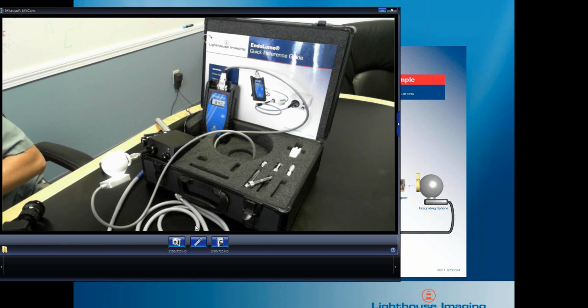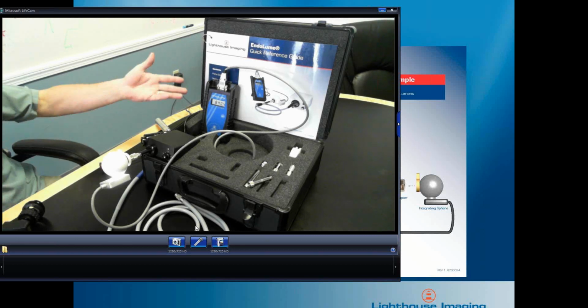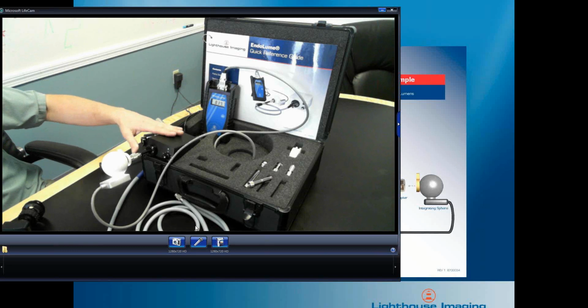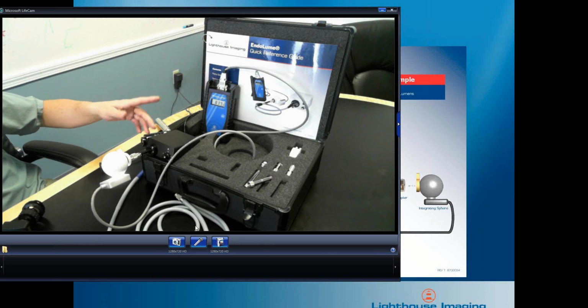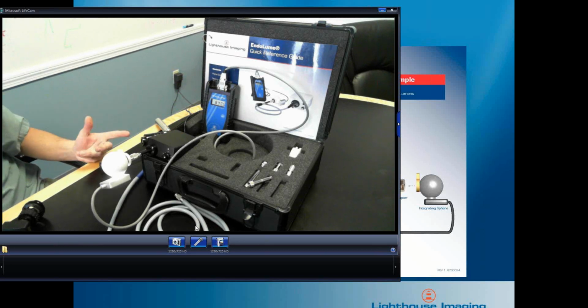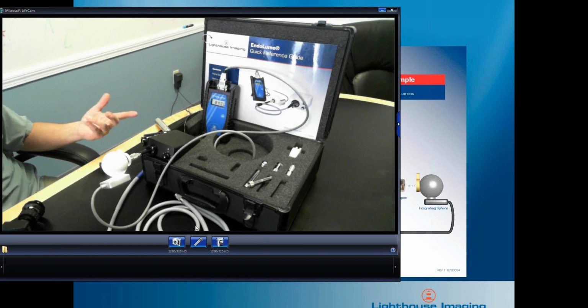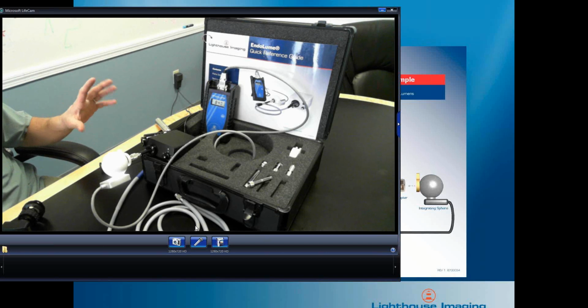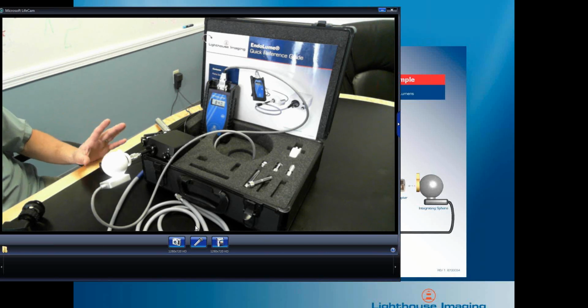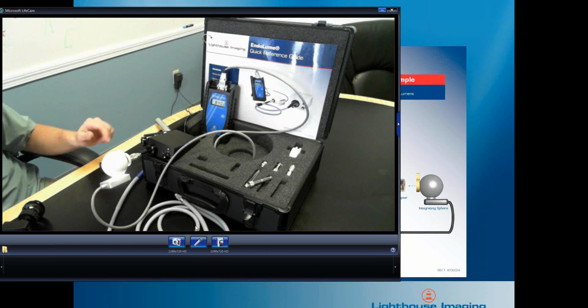Depending on the light source, this is an LED-based light source. That's actually a very good output for this small light source. But that's my basic measurement now. It's 840 lumens. If this were a 300-watt xenon light source, I would say the bulb is about to go bad, because this would be a low output for a 300-watt xenon. Again, if we remember that graphic that I showed before, it really should be 1,000 or 1,100 lumens minimum for a xenon light source. But this is actually a very good output for an LED light source.